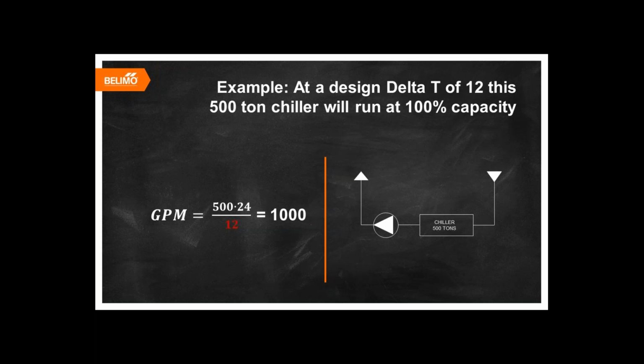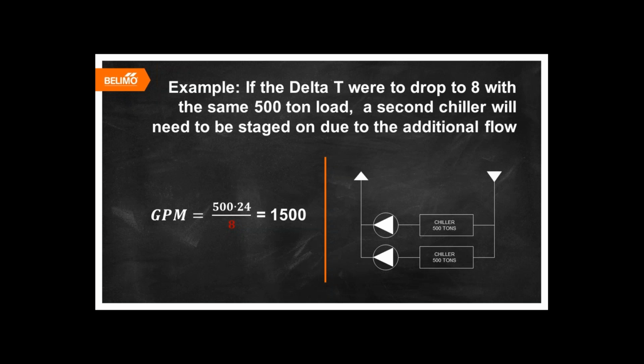What would happen to our chiller plant if our delta T were 8 instead of 12? Using the same formula, we can see that we need to stage a second chiller because we've increased our flow from 1,000 GPM to 1,500 GPM. So in order to maintain the same 500-ton load, a second chiller will need to be staged due to additional flow, not because of additional demand for cooling, but because we're flowing far too much water through the system. Running extra chillers and pumps when not necessary are common problems with buildings that suffer from low delta T syndrome.